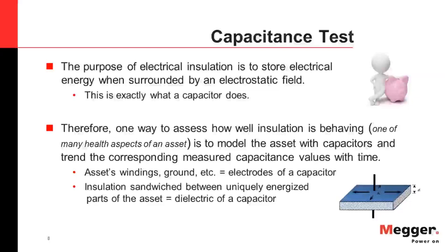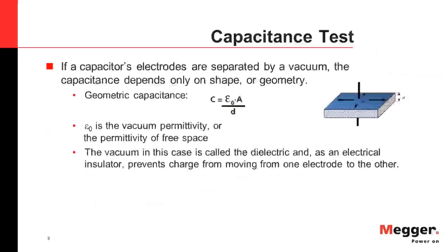Since capacitance is describing how an insulation system ideally behaves, and we are monitoring the measured capacitance values with time, we look to the equation of capacitance to learn more about the parameters that may cause a change in capacitance.